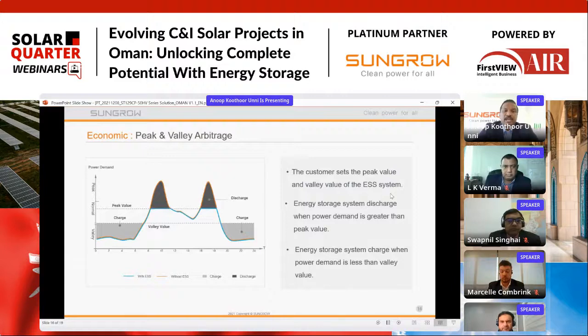In peak valley arbitrage, basically some clients have to pay more for power during peak consumption periods, for example day times 8 to 12 and evening 6 to 8. So the system will charge during low or off-peak times from the grid or another source, especially grid only, since there's no solar in that range, and it will discharge during peak hours so you can reduce your power tariff payments. This is called peak and valley arbitrage.